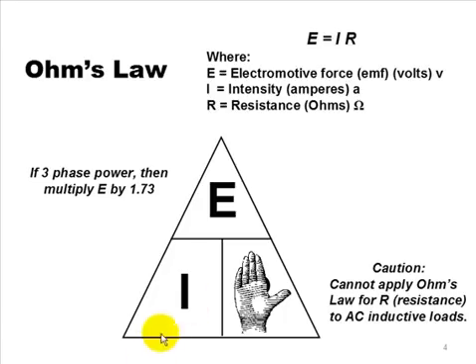And what a coil is, is a source of magnetic energy. Because as you run current through there, you create a magnetic field around those conductors, that winding. That inductance actually opposes the flow of current through that actual wire. It opposes itself. And because of that, Ohm's Law can't apply to any kind of inductive load. Because if you take any motor, take any motor on your shelf, doesn't matter whether it's PSC or whatever, and read the volts times amps and do the math, you're not going to come out.